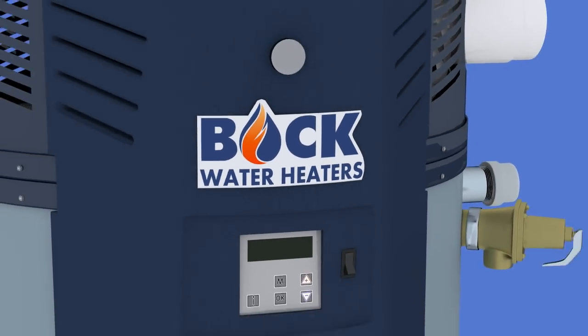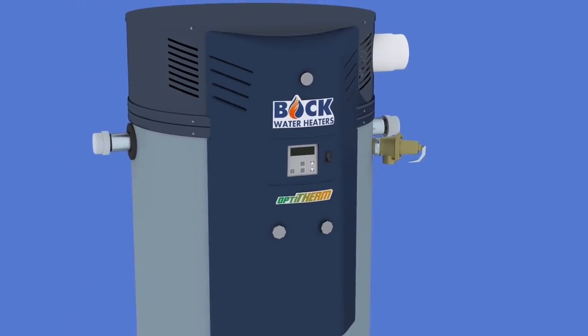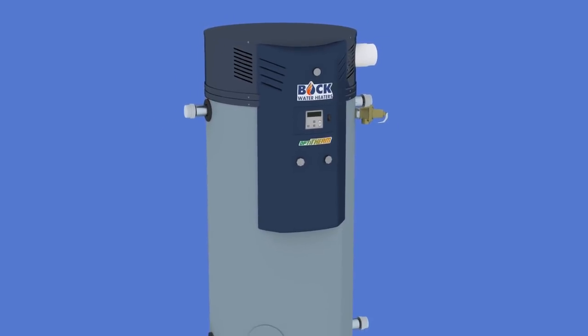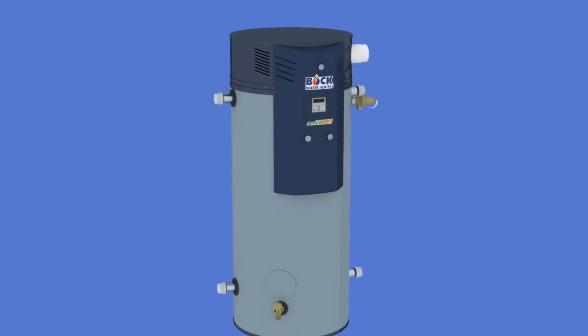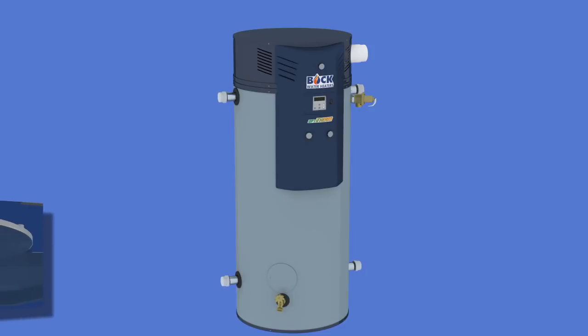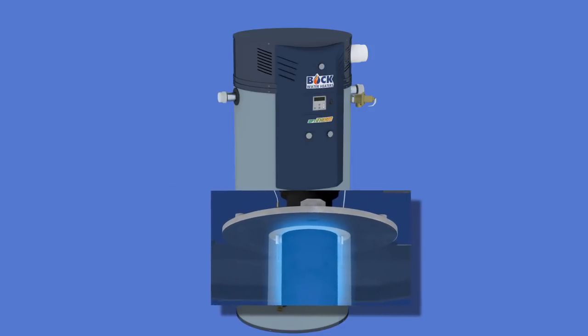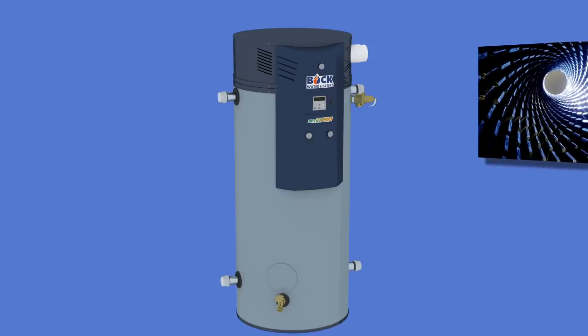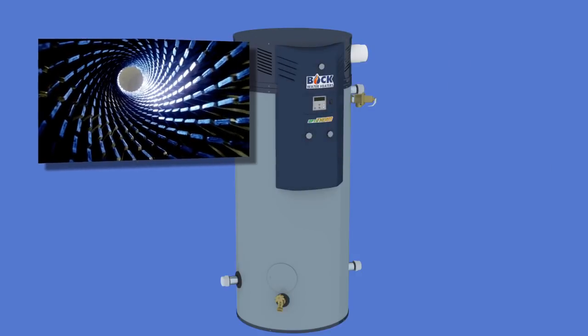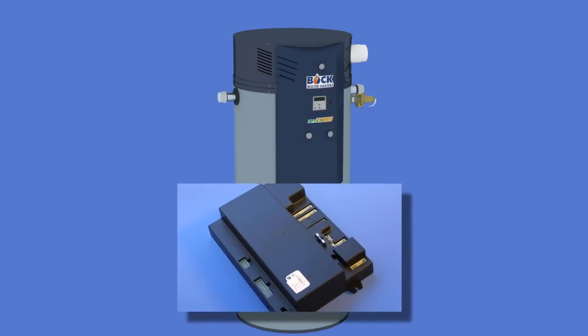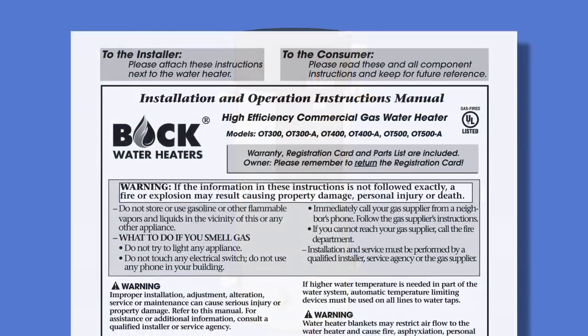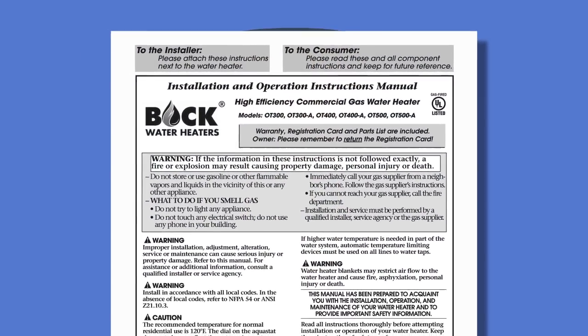The Bock optiTHERM represents the best and most efficient modern water heater technology, which provides lower operating costs and increased reliability. The optiTHERM achieves this by using a modulating gas burner, Bock's patented helical finned heat exchanger, and a precise microprocessor control. This program is not intended to be used in place of the manual.